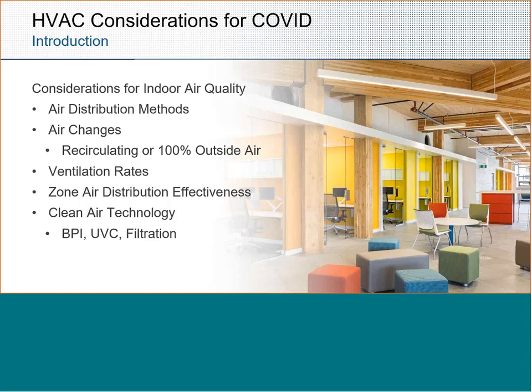But those are different air distribution methods that, within the space, directly impact how the contaminants, heavy and light particles, move throughout the space, as compared to, say, adding filtration or adding different clean air technologies into the ductwork, whether it be UVC or bipolar ionization. Those are good supplemental opportunities to introduce into the space, but the air distribution methods also have an additional impact that is really independent from the upstream system and air changes.